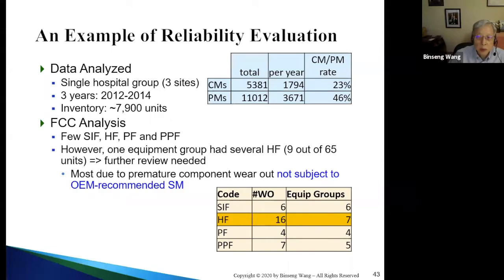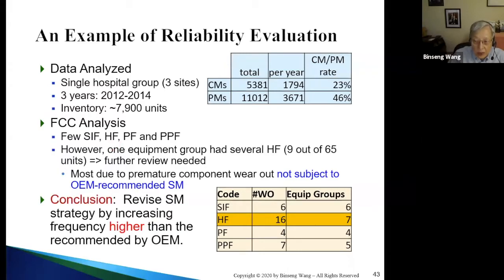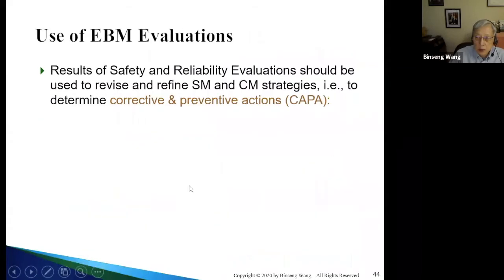It's even now used in the pandemic when you don't have a reliable oxygen source. And what we found out is that this particular brand and model of oxygen concentrator has a molecular sieve bed that needs to be replaced in theory every 10 years. However, when it's used in a humid and dusty environment, like many nursing homes, this molecular sieve bed will go bad more quickly. So we had to revise the scheduled maintenance strategy by increasing the frequency from 10 years to 5 years, therefore reducing the amount of hidden failures that this was displaying.